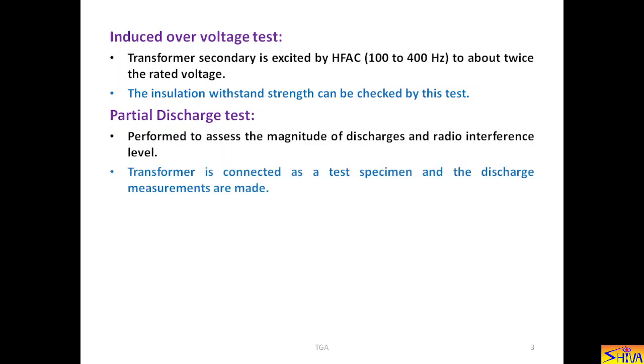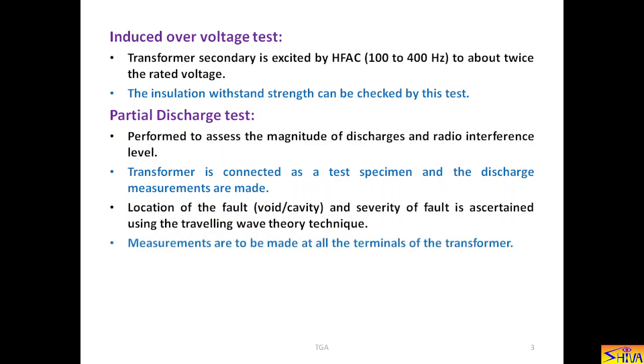Transformer is connected as a test specimen and the discharge measurements are made. Location of the fault, that is void or cavity and severity of fault is ascertained using the traveling wave theory technique. Measurements are to be made at all the terminals of the transformer.